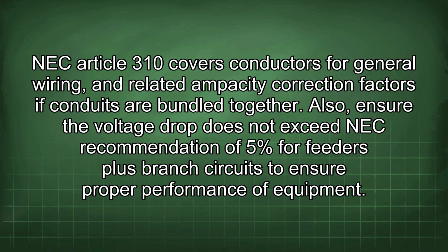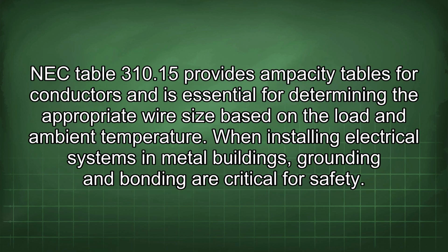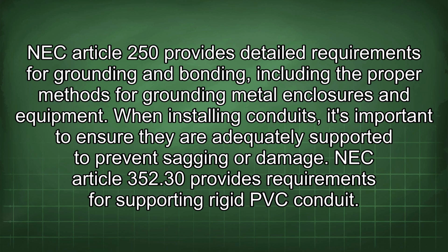NEC Article 310 covers conductors for general wiring and related ampacity correction factors if conduits are bundled together. Also, ensure the voltage drop does not exceed NEC recommendation of 5% for feeders plus branch circuits to ensure proper performance of equipment. NEC Table 310.15 provides ampacity tables for conductors and is essential for determining the appropriate wire size based on the load and ambient temperature. When installing electrical systems in metal buildings, grounding and bonding are critical for safety. NEC Article 250 provides detailed requirements for grounding and bonding, including the proper methods for grounding metal enclosures and equipment.